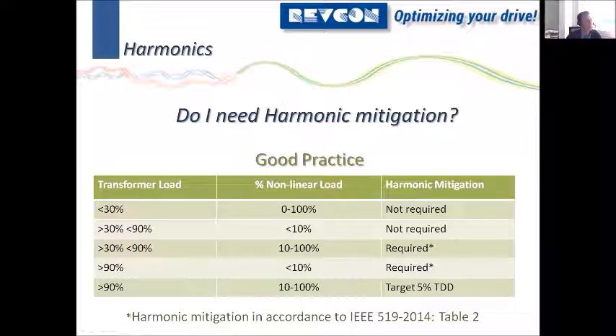Okay, so if you have a transformer and it's loaded below 30%, you have nonlinear loads no matter how much. It could be 0 to 100%. So even if 30% of this transformer is with drives, you will not need harmonic mitigation. You're safe. If your transformer load is 30% to 90% and your nonlinear loads, meaning drive power or other nonlinear equipment, LED driver or whatever, are low, you will not need harmonic mitigation.